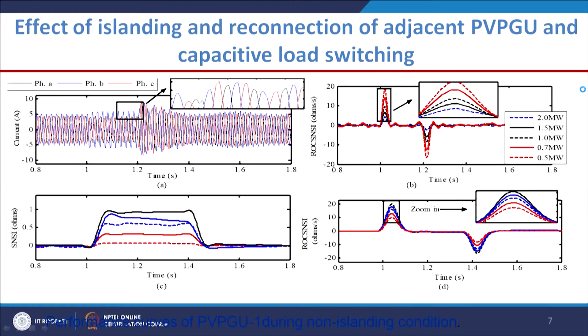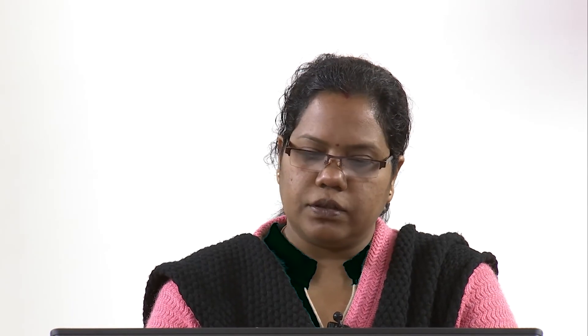For the capacitor switching and adjacent PV reconnection non-islanding event, the rate of change of superimposed negative sequence impedance remains within 20 — which means it is correctly not declared as an islanding situation. Testing for different types of capacitor switching confirmed that the value stays below the threshold of 20.